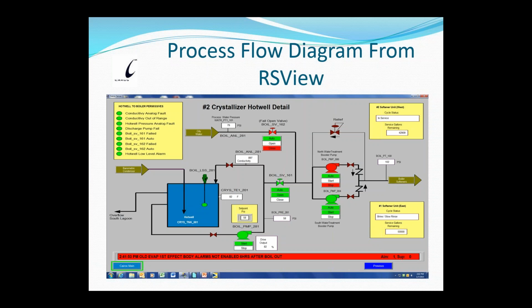When we set this up, we have these hot well to boiler permissives where the pump will not start up unless all of these are green. The pump will start up. It'll slowly ramp up to a desired set point pressure, which is right here. It's got a variable frequency drive on the pump in order to maintain a certain pressure point that I need, because I need that pressure to be able to feed not only enough water, but at a pressure that will give us the required pressure on our booster pumps to make it through the water softeners, and then still be able to provide the pressure needed for the RO train pumps. So what happens is this starts up, the pump starts up.